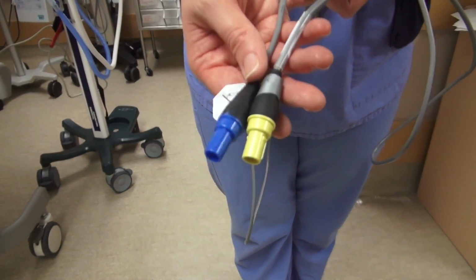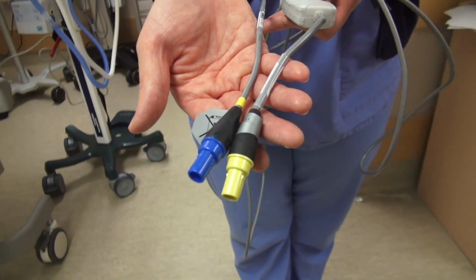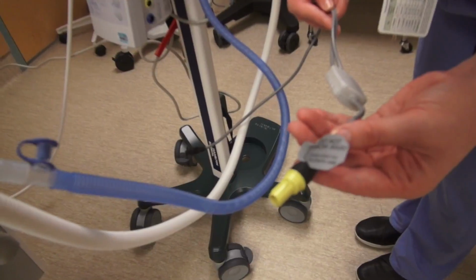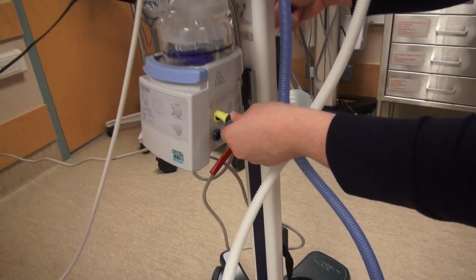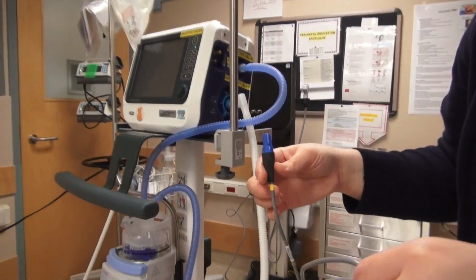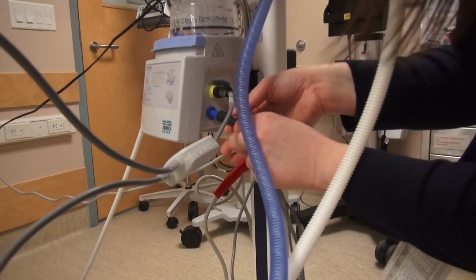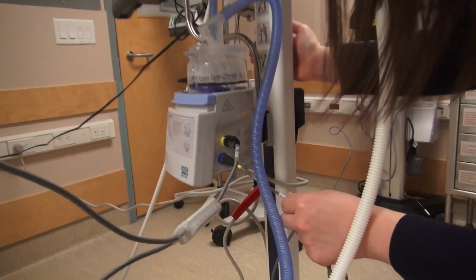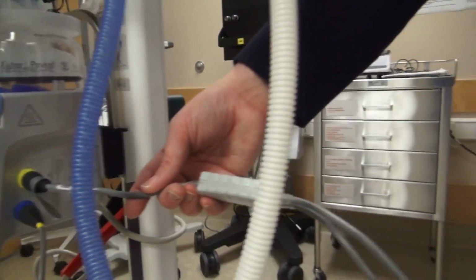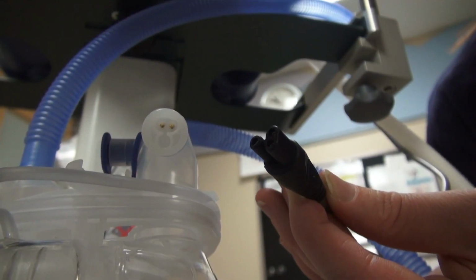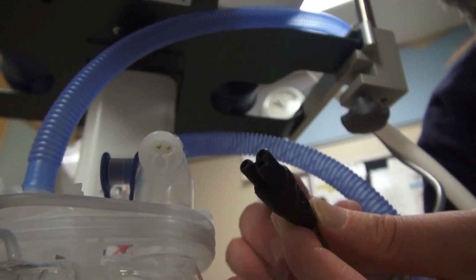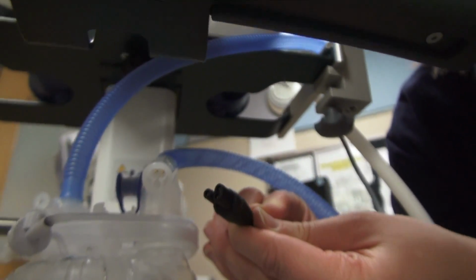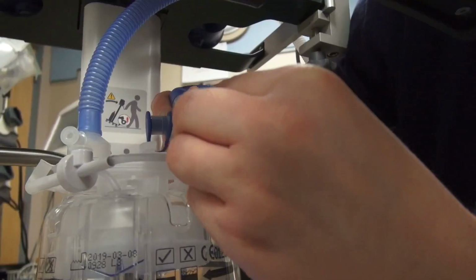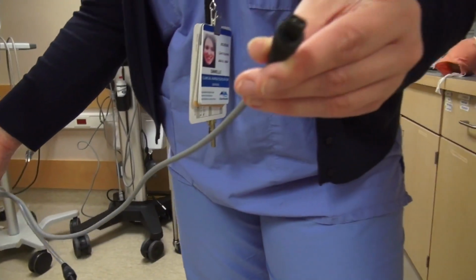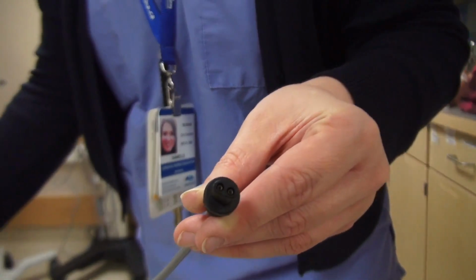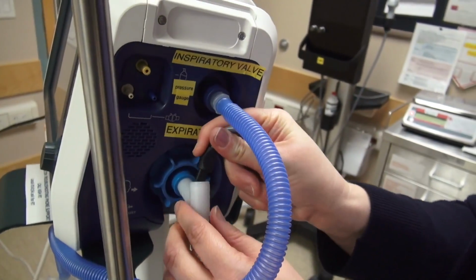Humidifier and temperature wire setup. There are two main wires attached to the humidifier pot, the yellow-ended one and a blue-ended one. Insert blue end of temperature probe, which will come sterilized from MDRD, into matching blue port on side of humidifier. Attach the 3-prong end from the yellow humidifier wire to the inspiratory tube connected on top of humidifier pot. Attach 2-prong yellow humidifier wire to top of white expiratory tube.